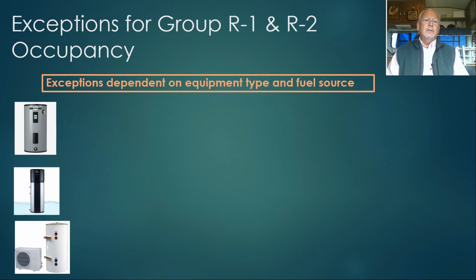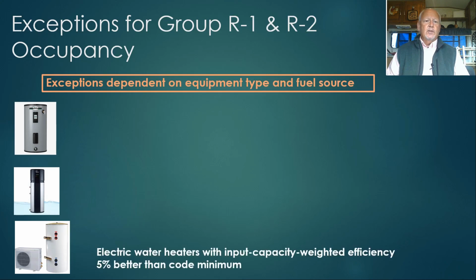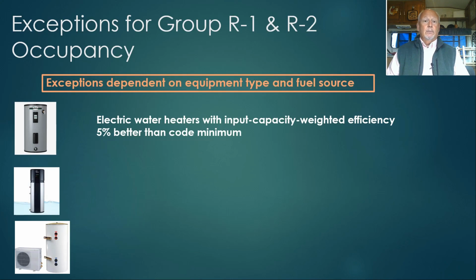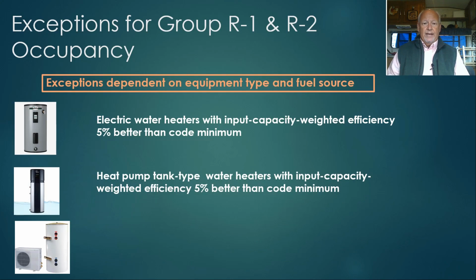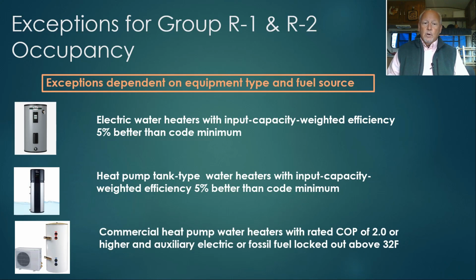Again, there are exceptions for this requirement depending on the type of hot water system that's in the building. If you have single electric water heaters in your Group R1 or Group R2 building, if you install electric water heaters with an input capacity weighted efficiency 5% better than code minimum, you're exempt from that requirement. If you have heat pump tank-type water heaters that are 5% better than code minimum, you can also be exempt from that requirement. If you have commercial heat pump water heaters with a rated COP of 2.0 or higher and auxiliary electric or fossil fuel locked out above 32 degrees, you can also be exempt from this requirement.